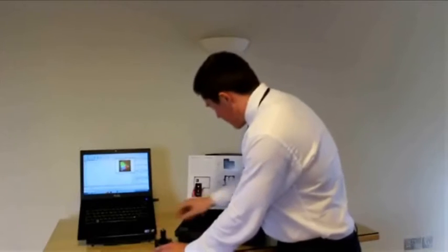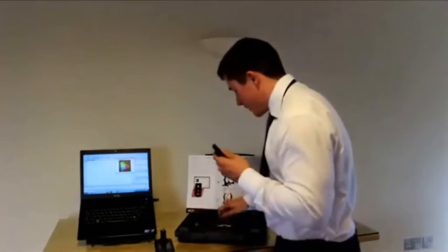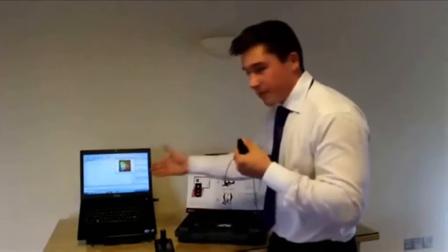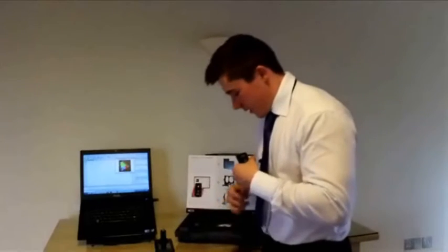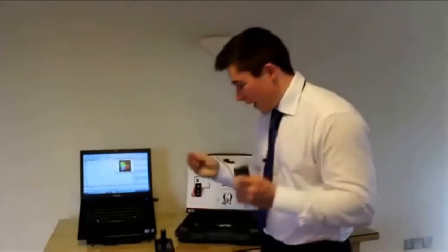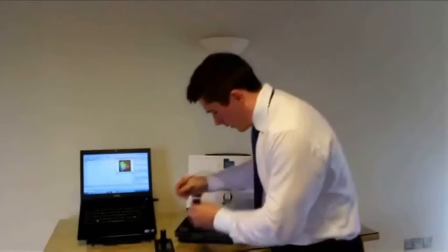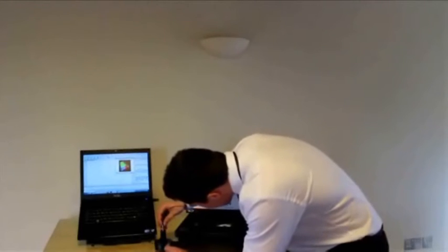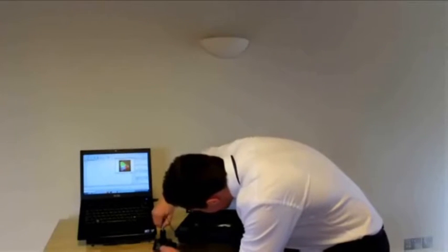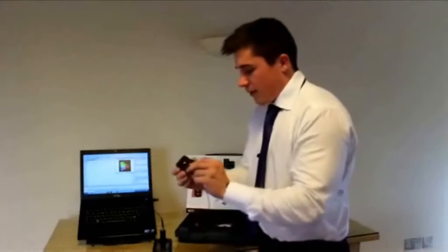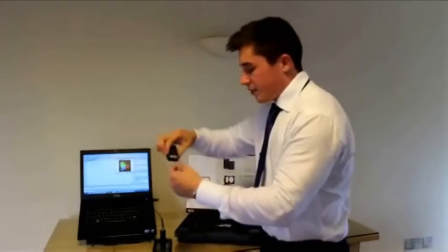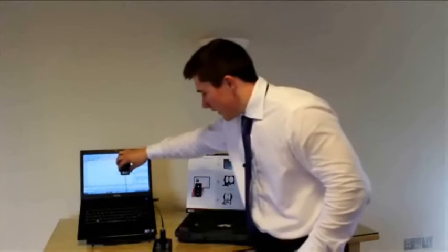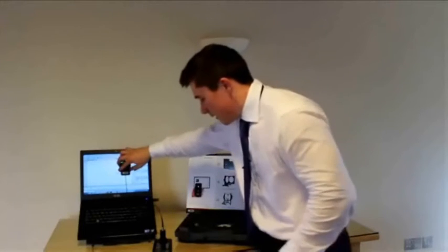This is used to accurately measure OLED displays and screens such as my laptop screen here. The device is connected through a fibre optic cable and I'll simply just attach it as shown. This can be placed in a tripod at fixed distance from your screen or you can just hold it against the screen here.